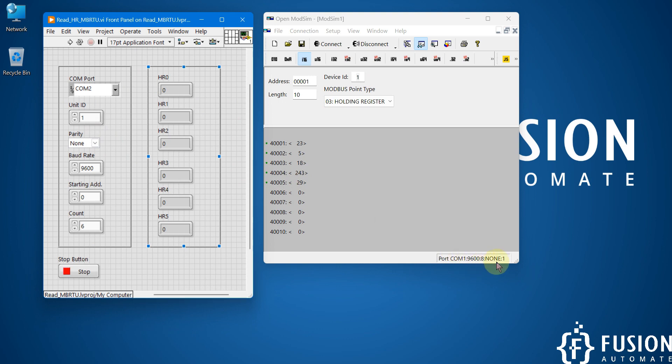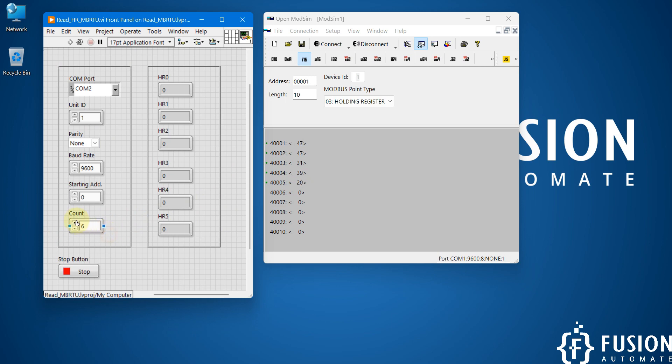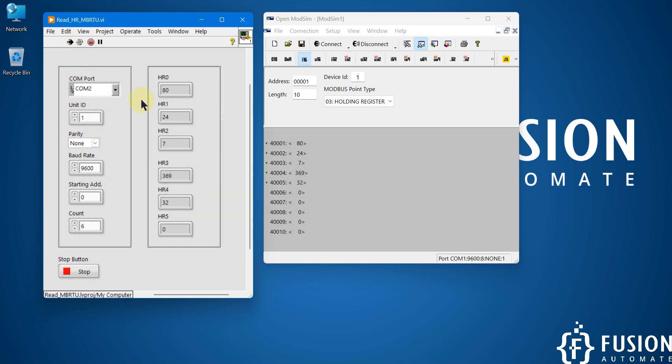The parity is none as you can see here. The baud rate is 9600 and we are going to read the data from starting address zero, I mean 40000, and we are going to read six holding registers. That's why we have to specify the count six. After that you just have to start your LabVIEW project and it will read the data continuously.